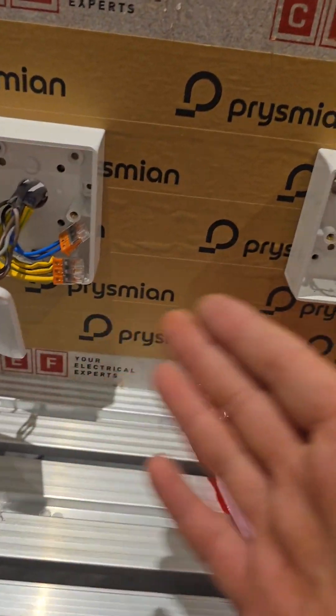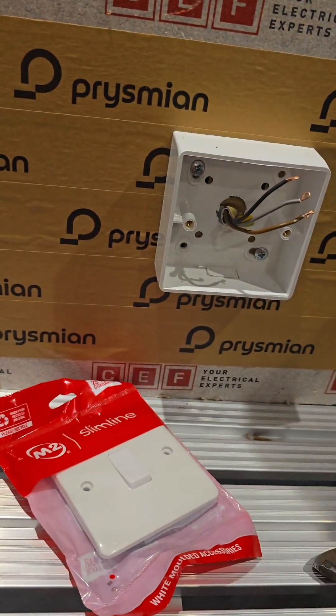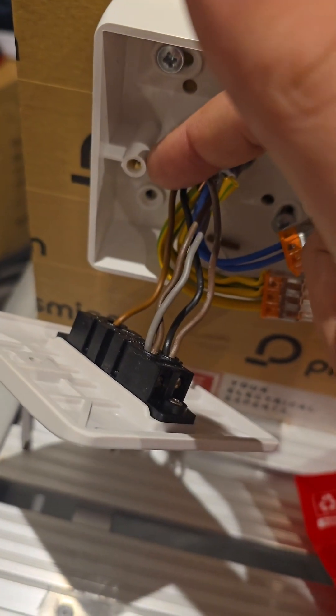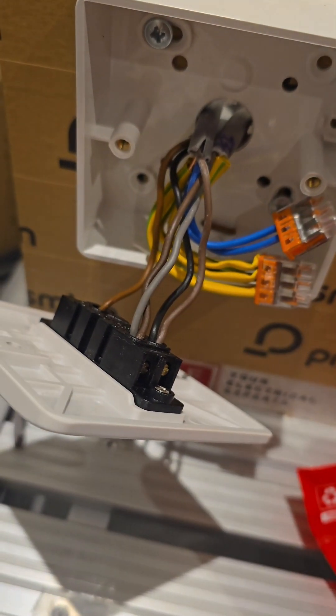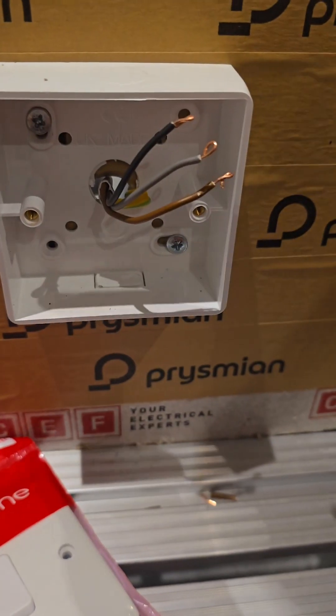Absolute rookie move - was going to film another two-way, picked up an intermediate, but it doesn't matter because I'm a genius. Two-way setup from your three core: you've got brown in common, gray in L1, black in L2. They should be sleeved. You've got your feed in L1 and your load in L2.